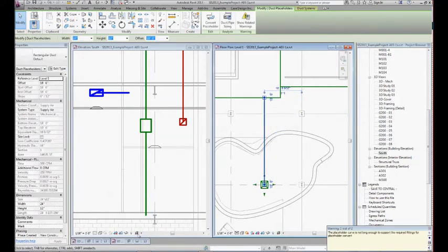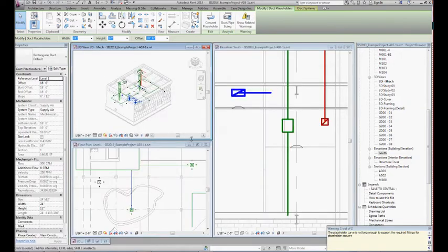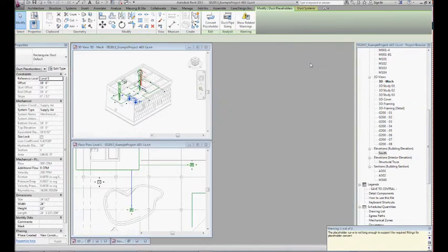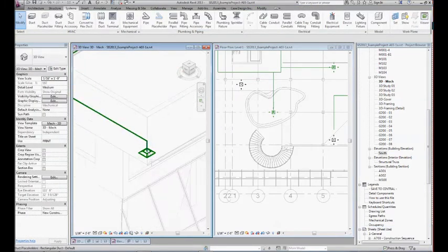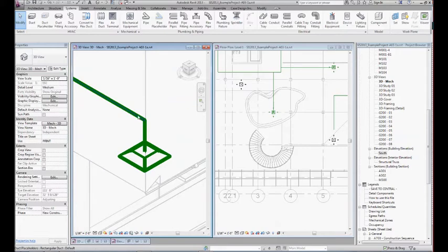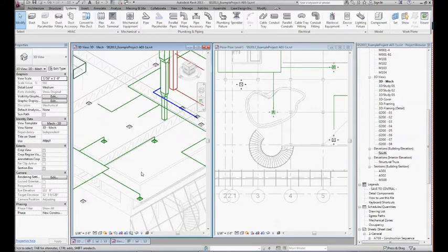And just so you see what's happening, when I drag that over, sorry, I'm going to have to bounce around the screens a little bit here. When I drag that over, it's actually creating a little placeholder connection here. And once again, this is placeholder connection, so that's not really going to come down at a 90-degree angle. That's actually just standing in for the fitting that will eventually be here, which will be a nice smooth radius, because air, just like water, wants to flow through a nice smooth path and not go through kind of a corner.